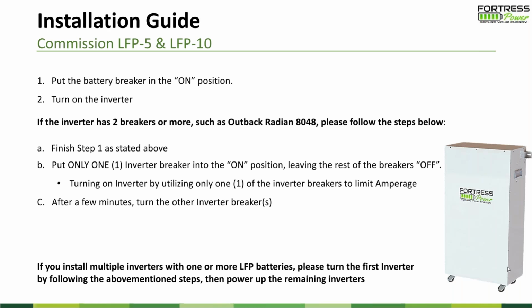For example, one is 51, the other is 51.2. That's perfect. You don't want to see one at 51 and the other at 53. Once you start the system, one battery is going to charge the other battery, and with lithium batteries, 2 volt means a lot. There's a lot of capacity in 2 volt. It can damage the battery cells, and can usually damage the BMS. We don't want to see that happen. Just make sure you check it before that. Once you wire up the system, you usually turn on the battery's circuit breaker, and then you can start your inverter. The inverter will start once it has the 48 volt power coming in. That's how you finish the commissioning of the system.